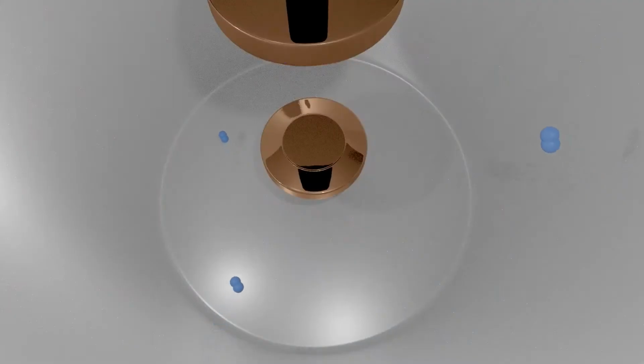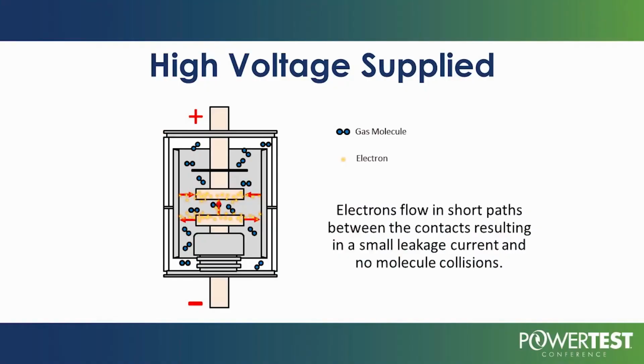These gas molecules can be noble gases, they can be gases that are not stable, or some of either one. That depends on the number of electrons in the outer valence shell. What we really want to affect are the unstable gas molecules, because for the noble gases the outside shell is already full, and they're very hard or impossible to deal with. So we can never get the pressure to zero, but we can keep the pressure in a range where it will operate correctly. What we do is apply a high DC voltage.